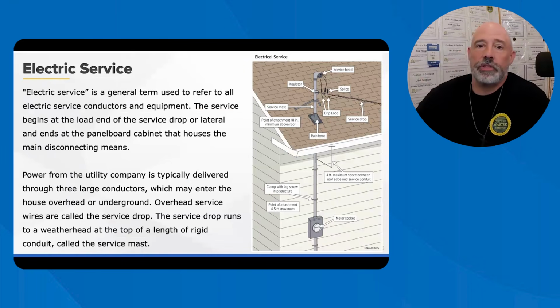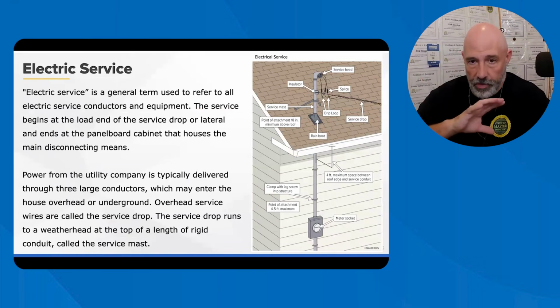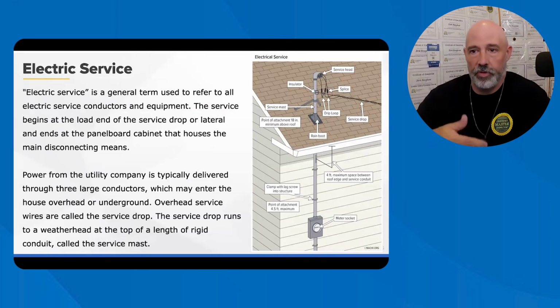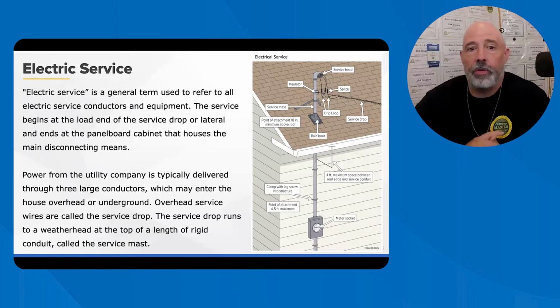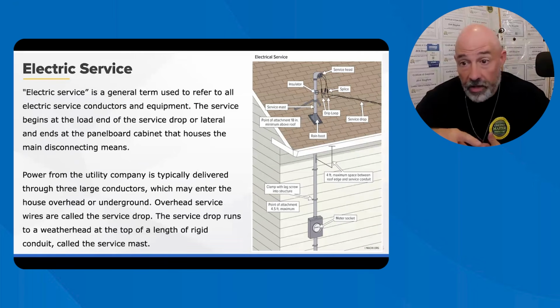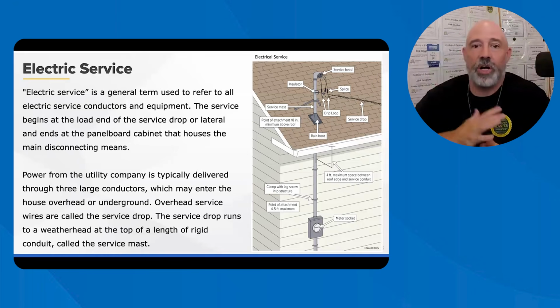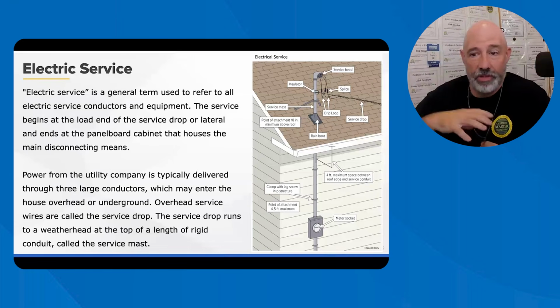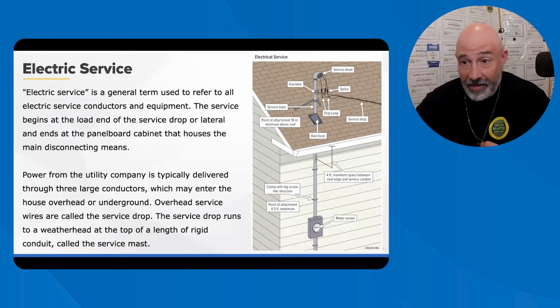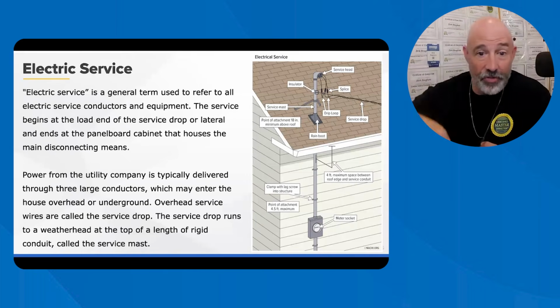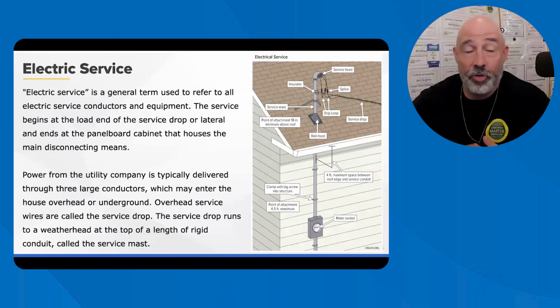Electrical service refers to the conductors and equipment that deliver the power from the utility to the home, up to the main service panel and the main disconnect. Power is typically supplied by three conductors entering the home either overhead or underground. We all know this. Overhead conductors are called the service drop. Make sure you keep that in your head. It should be connected to a weather head and travel down the service mast into the electrical panel.